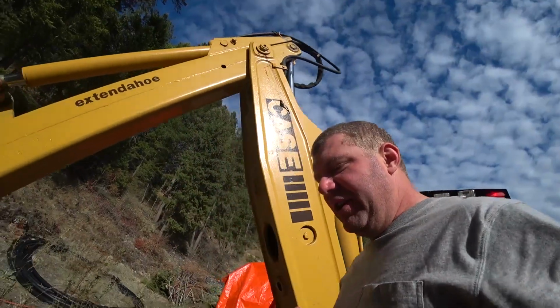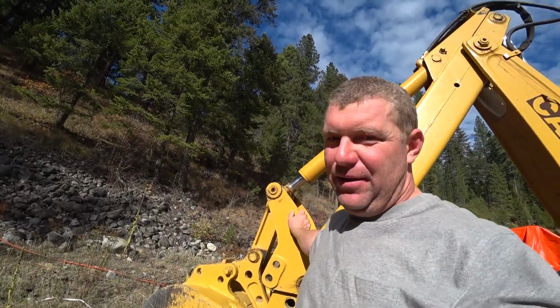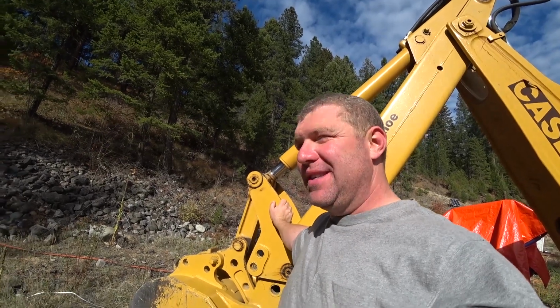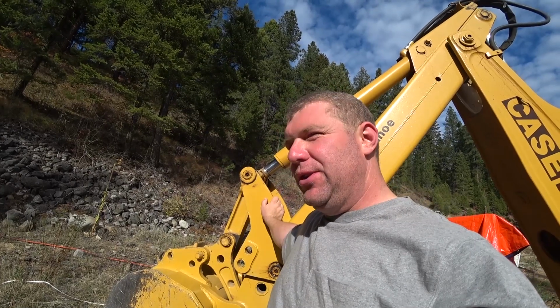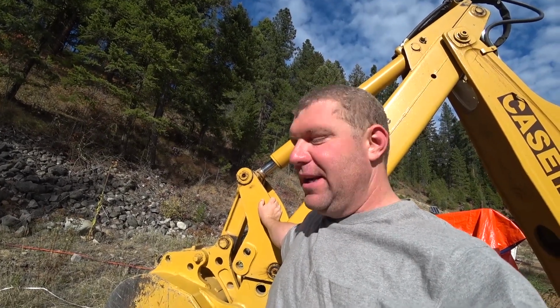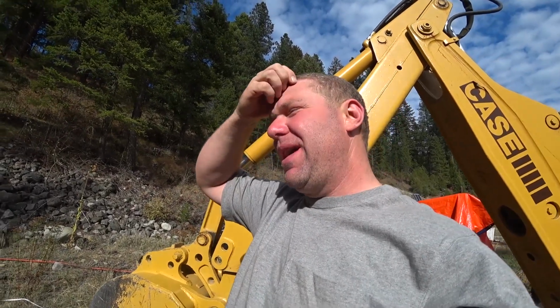So I forgot to mention earlier that I believe electrical code says that in order to be legal, your conduit must be 18 inches to the top of the conduit. And I believe we're burying 2.5-inch conduit just to make the pull easier. Conduit's pretty cheap. 2.5 inches generous. So I think that's what we're burying here.